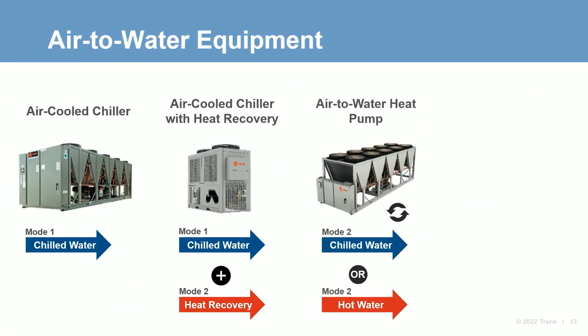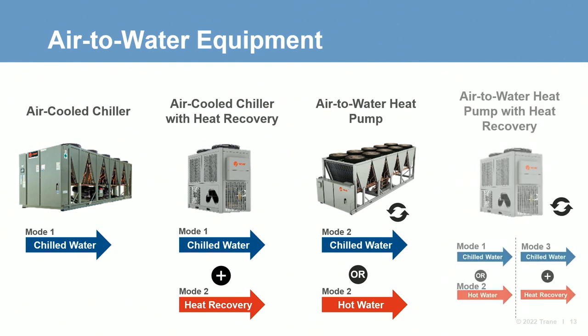The third category would be air-to-water heat pumps that utilize a reversing valve to allow the unit to use the ambient air as both a source and a sink for BTUs, meaning it could change modes to provide either cooling or heating throughout the year. The last unit combines the air-to-water heat pump with a heat recovery heat exchanger. This unit would be able to act like a heat pump to provide either cooling or heating. Then it could also provide recovered heat from the cooling load if the building has simultaneous cooling and heating requirements. Now, the basis of this CNL will focus in on air-to-water heat pumps and how to properly apply them. But we'll also show various ways to incorporate these other technologies throughout the presentation.